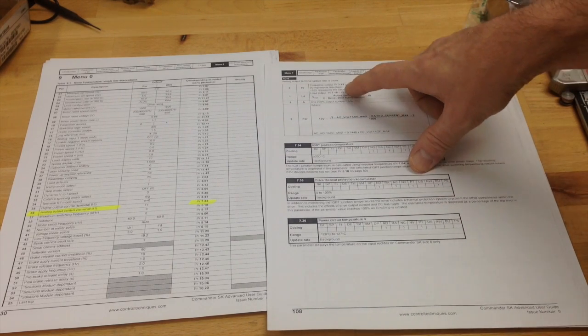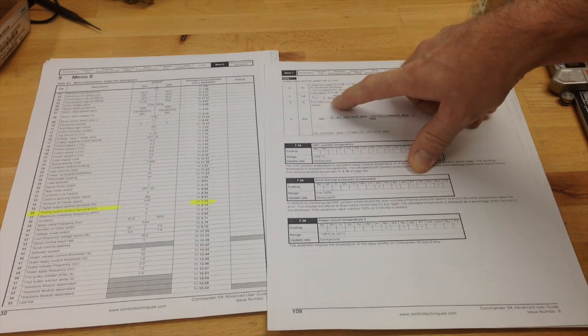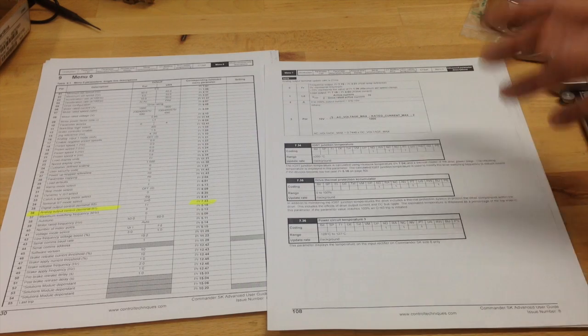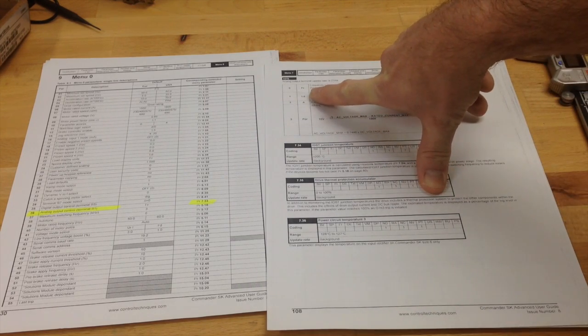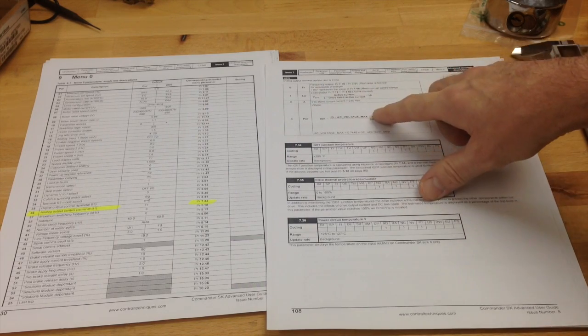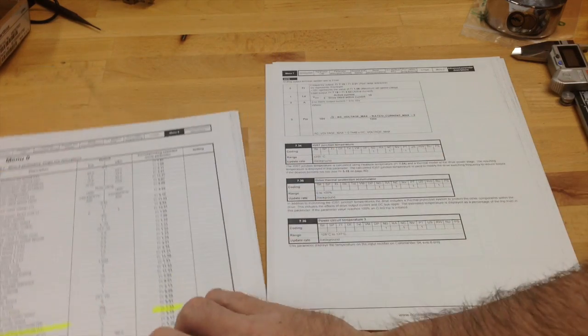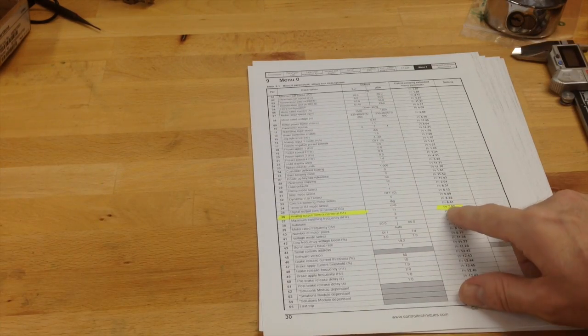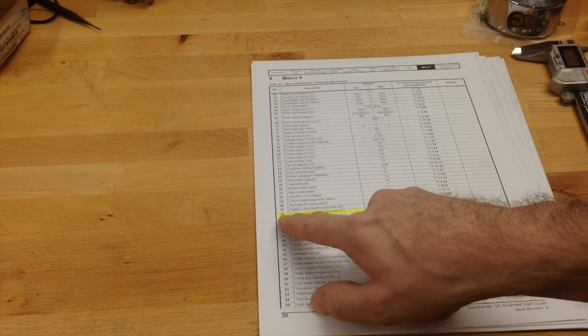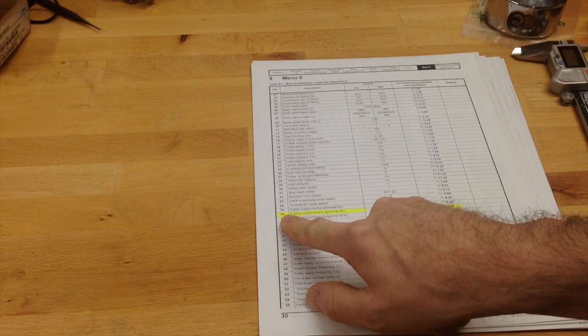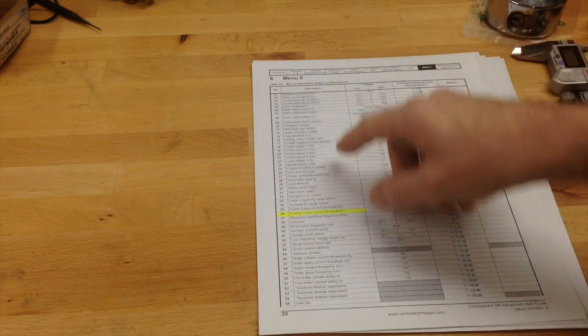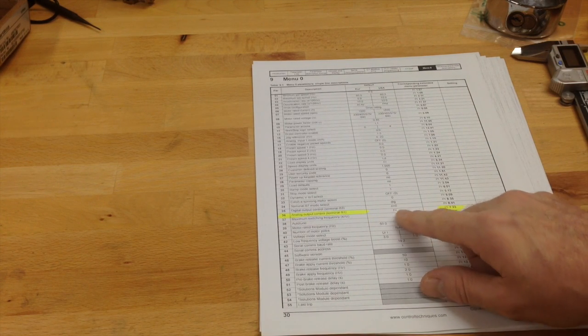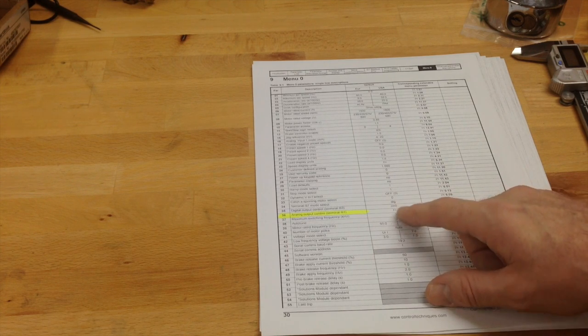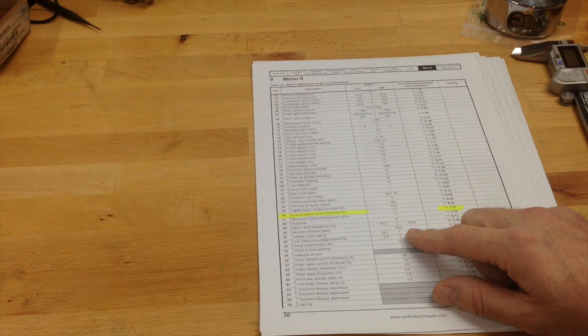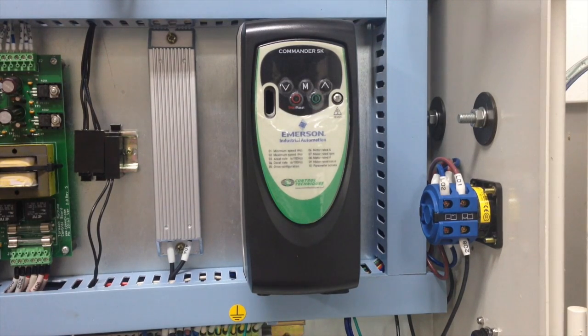There's not a lot of difference, to be honest, between load and the LD and A option, or load and current option. One's active, one's reactive current. I'm choosing to use the load function. So how do we access advanced parameter 7.33? Well, page 30 of the manual tells us as well that parameter 7.33 is also the same as parameter 36 from the front panel of the VFD. So all we need to do is go down to parameter 36 on the front panel and choose between frequency, load, current, and power to select which reference voltage we want to output. Okay. Right, this last step, we're going to program up parameter 36 and then get this load meter wired into the VFD. Okay.